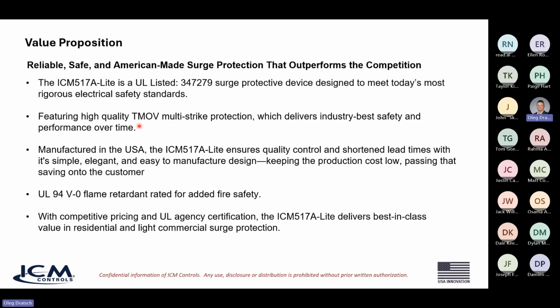We mentioned it before, we'll say it again: the UL listed device, listed under 347279. It is tested to the UL standard 1449, the 5th edition. Some of the competitive products are tested to the 3rd and the 4th edition. The 5th is the most stringent, providing the most safety and the most performance. It is manufactured in the US, unlike most of our competition as well.